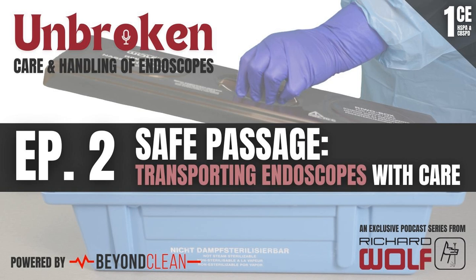They opened the door and the scope was just sitting on the shelf of the case cart and a bunch of other stuff, and it trickled out and fell on the floor and broke. The techs get those in decon, and they see that note. So that's where it really starts the process, because if it's not documented as broken, or our techs don't do a good investigation or evaluation on the scope in decon, then that's going to get cleaned, pushed through, and hopefully during another inspection and assembly it gets identified that there's an issue with the scope. So the whole process is very lengthy just before it even gets to the leadership end, if it's identified.